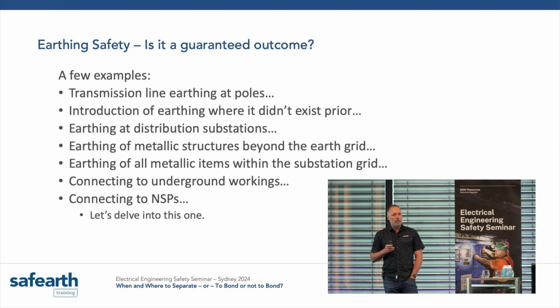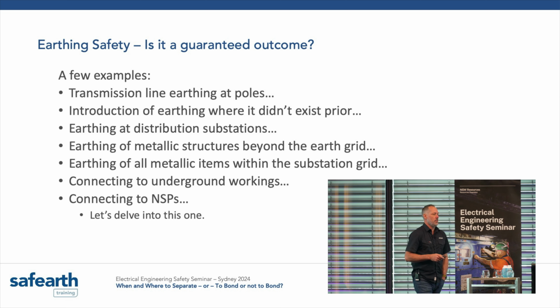Transmission line earthing is a complex job because it's really all about lightning protection for the lines and keeping the equipment working. We earth the structures to the earth wire so that lightning transients have a nice low impedance path to ground, so they don't create over voltages, don't stress insulation, and don't create earth faults on our major transmission systems like our 500 and 330 kV systems.